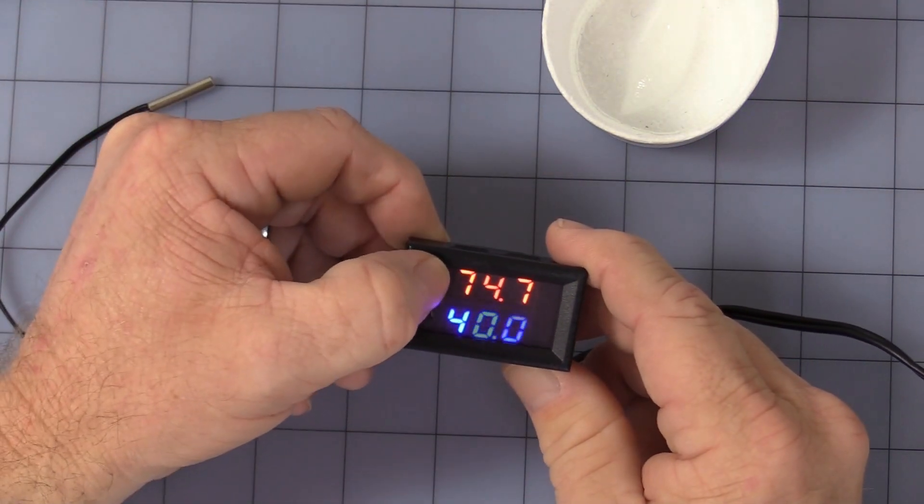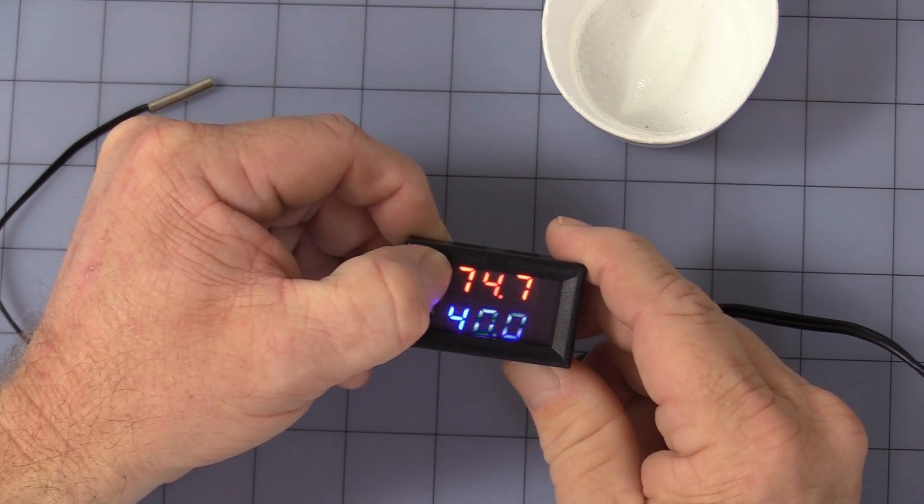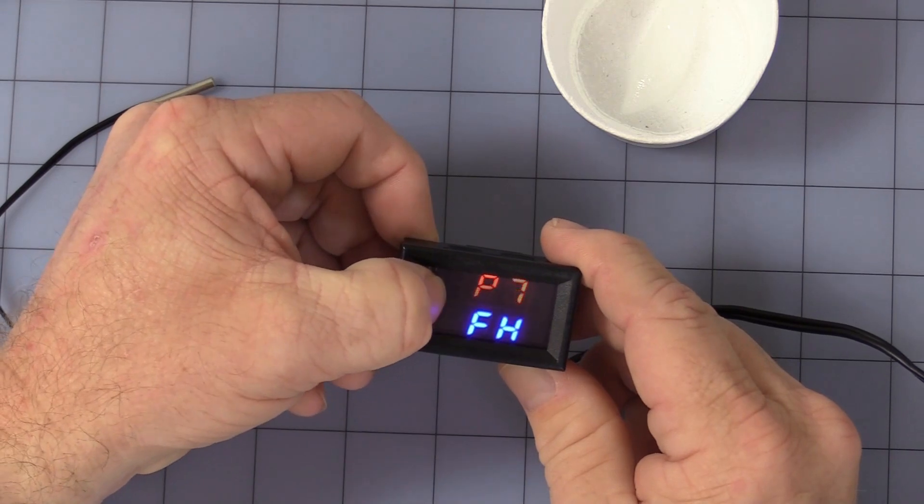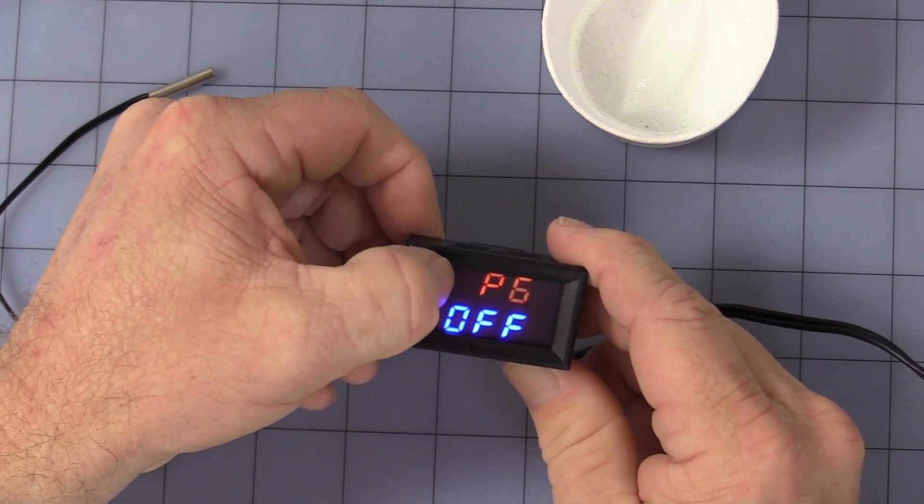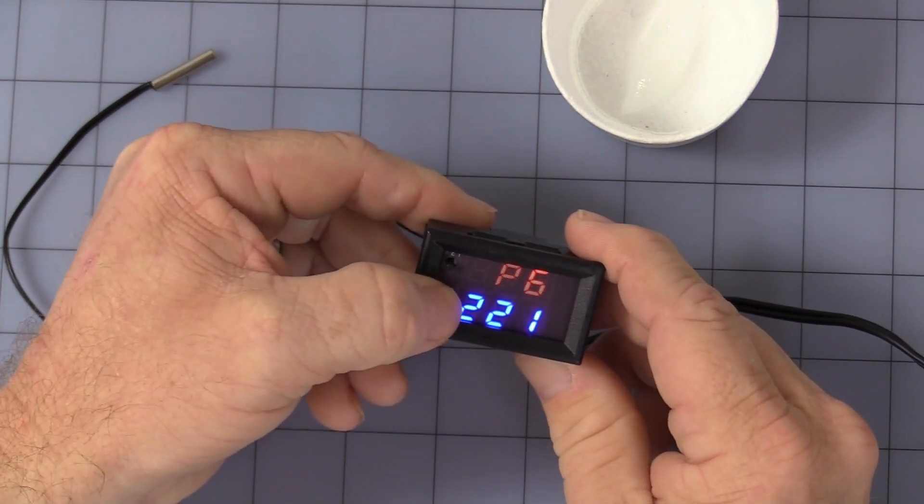Now, we get into P6, which is a high-temperature alarm. This is a little interesting and a little tricky. P6 comes turned off, press and hold both buttons, turn it on. While it's still flashing, press both buttons again, and it comes factory set at 230 degrees.